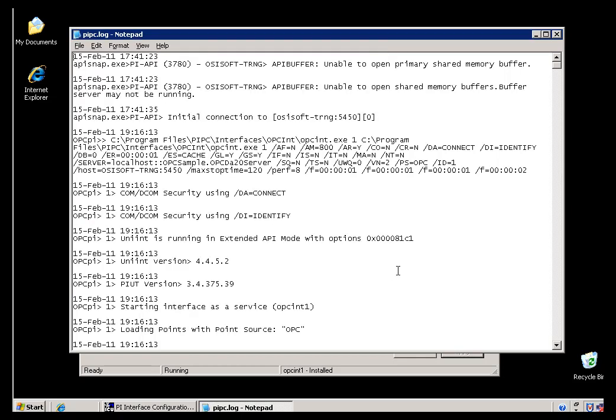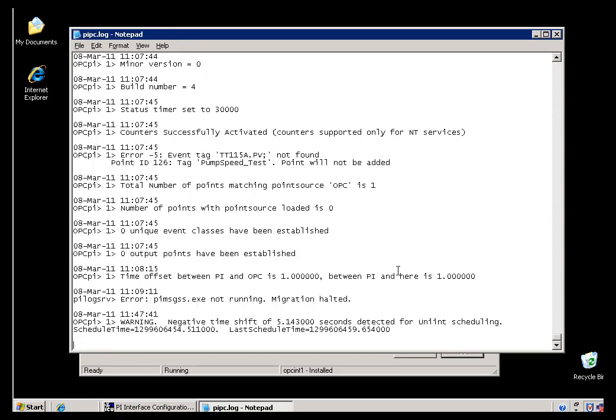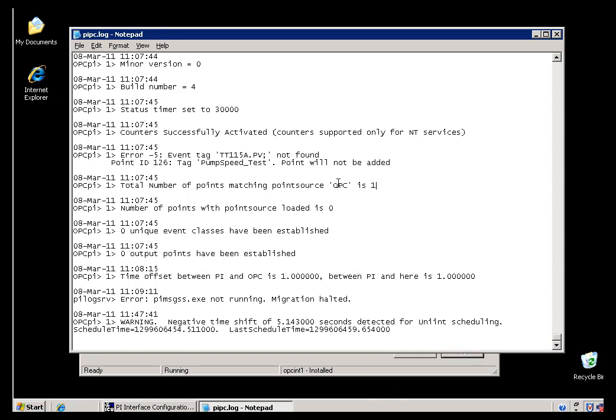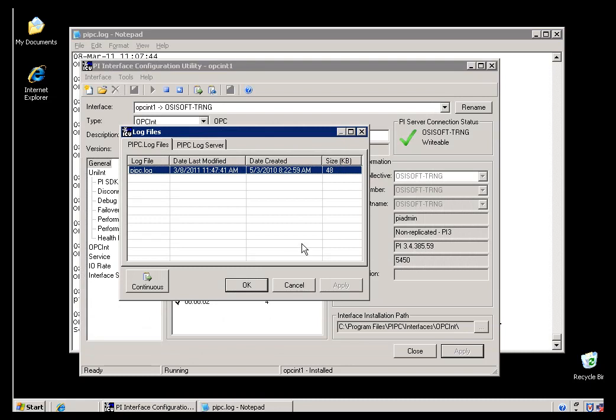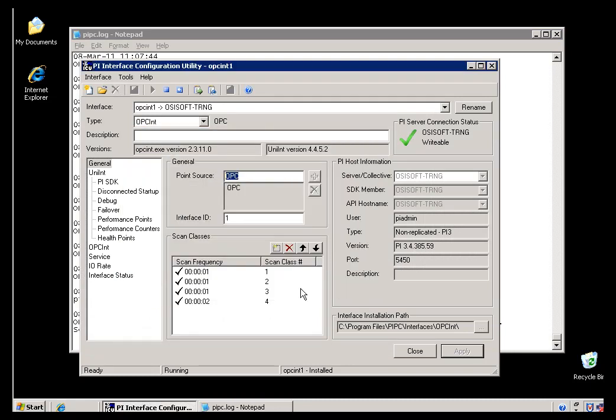What I'm looking for is the point in time when this Interface started up, and I'm looking for the number of Tags that it found that have that Point Source. If it didn't find any Tags, if the total number of Points were zero here, then I would probably go out and look to see if I used the right Point Source, because that Interface is looking for a couple of Matches. It's looking for a matching Point Source.